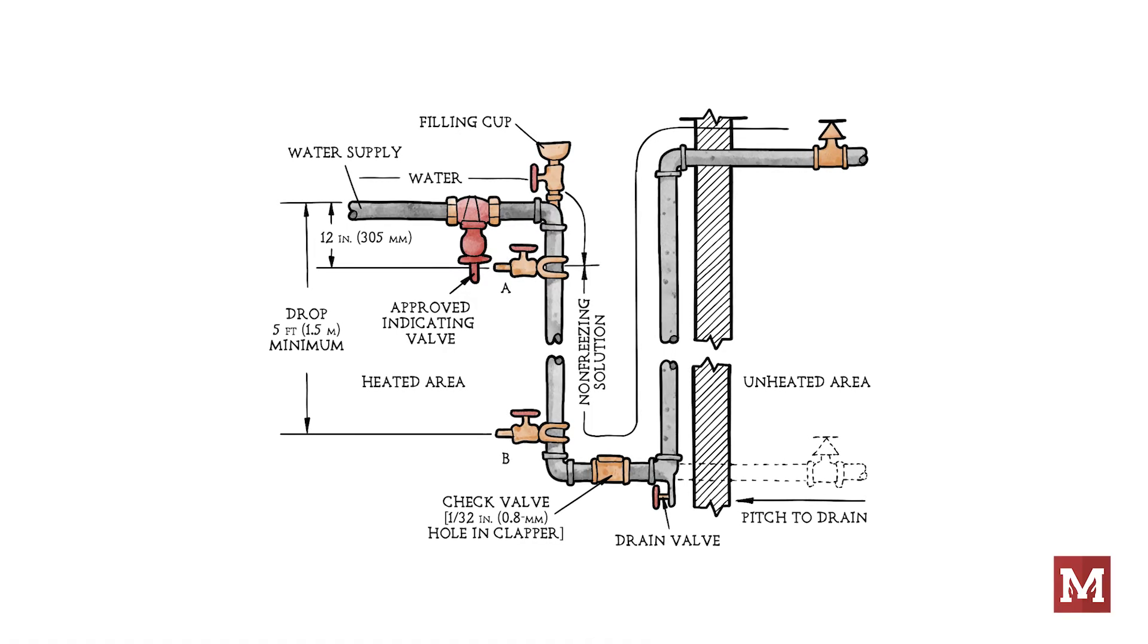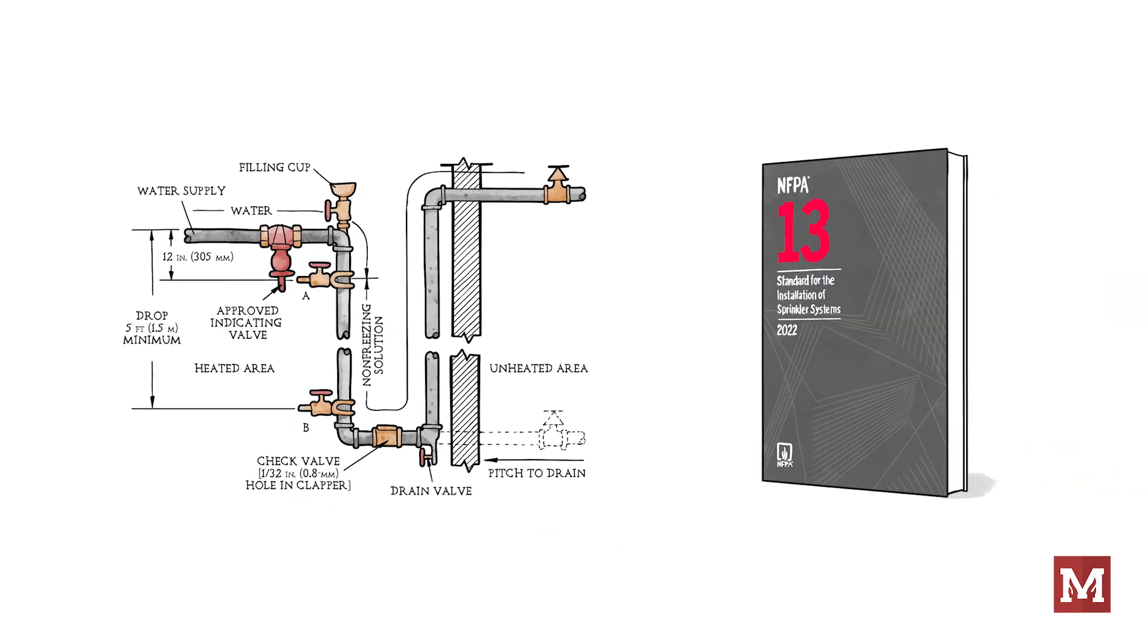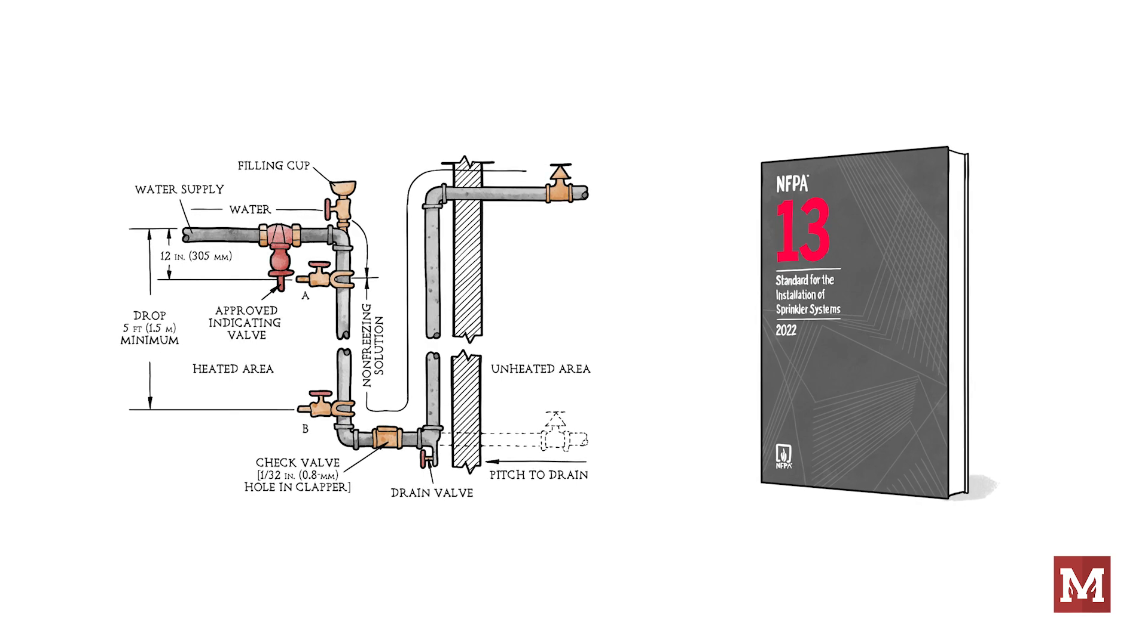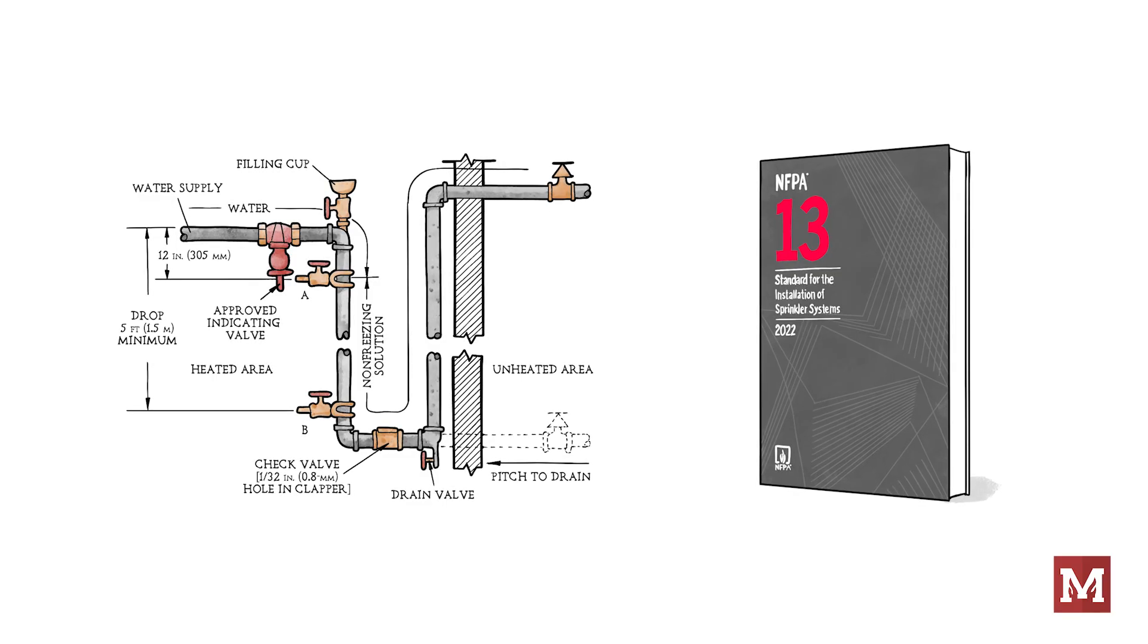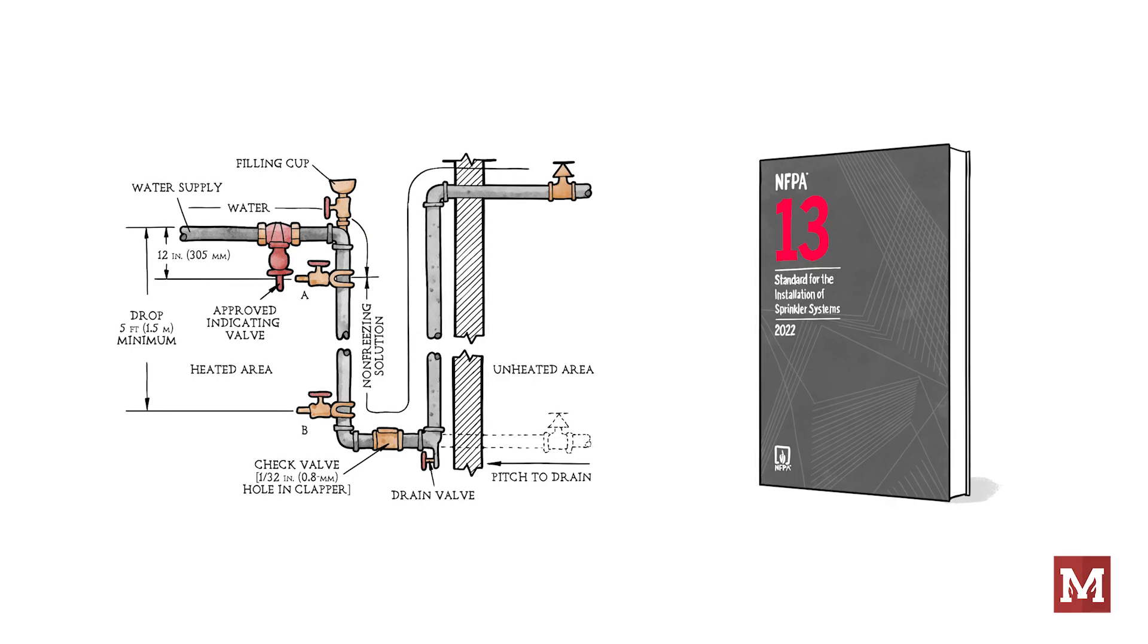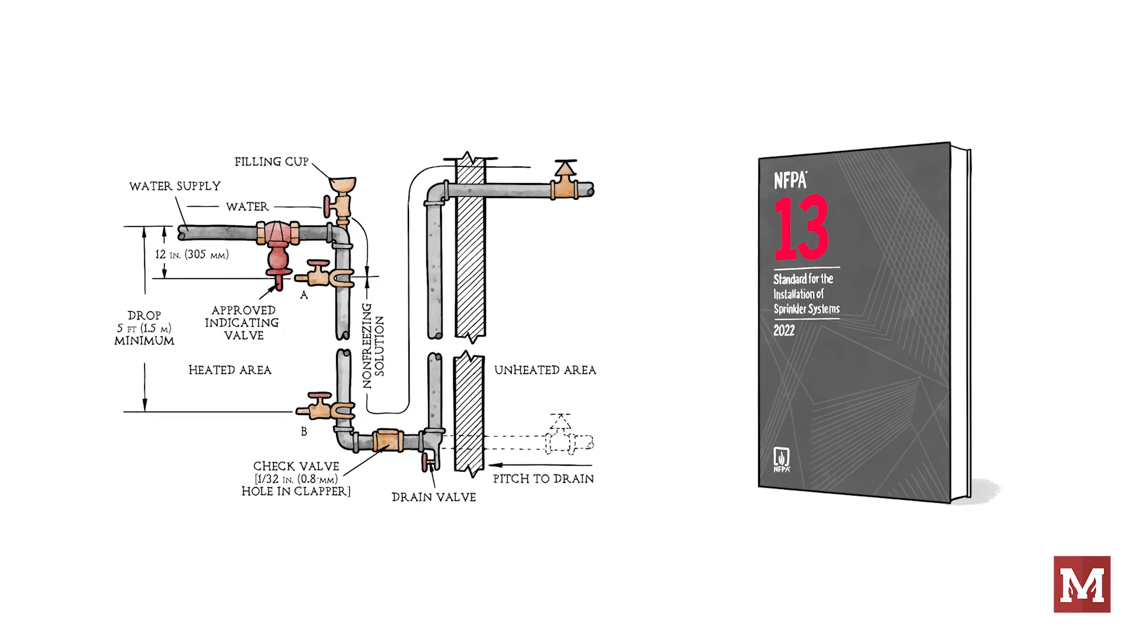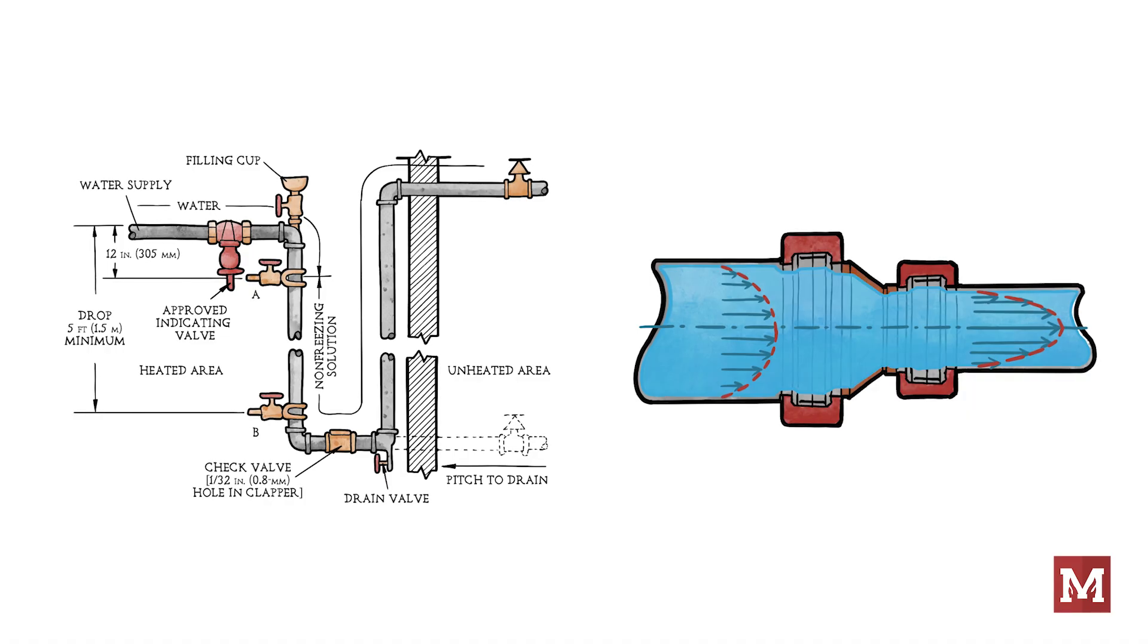For systems that use water only, the standard NFPA 13 does not mandate the use of Darcy-Weisbach because water maintains relatively stable properties—that would be density and viscosity—across temperatures typically encountered in fire protection. This stability means that the effects of turbulence on pressure loss are minor and the simpler calculations using the Hazen-Williams method are often sufficient. But when do I always use the more accurate method?